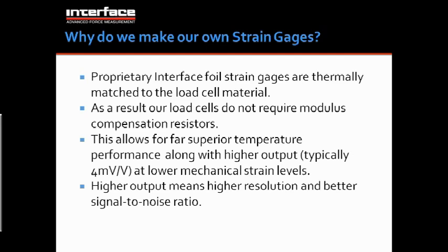Well, aside from very, very stable temperature performance, it also means that we're not taking any of that signal out of the sensor through the additional resistors. So you end up with more output. Majority of our low profiles are 4 millivolt per volt sensitivity. So higher output is going to mean better resolution for the test that you're trying to perform. So again, the reason we do it is to build a better product that ends up helping you guys as customers.